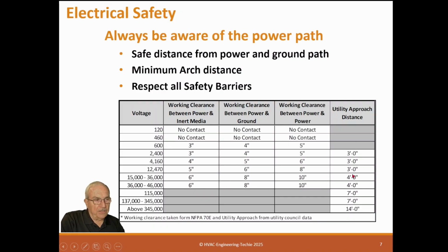Now, this utility approach data is what the utility says you should not be closer to the power feed than. And this is for the power coming into the site. So 3 feet for 2,400 volts. Utility distances aren't applied at these 600 volts because these are building voltages. But 3 feet going up to 15,000 volts is 4 feet. 115,000 is 7 feet.